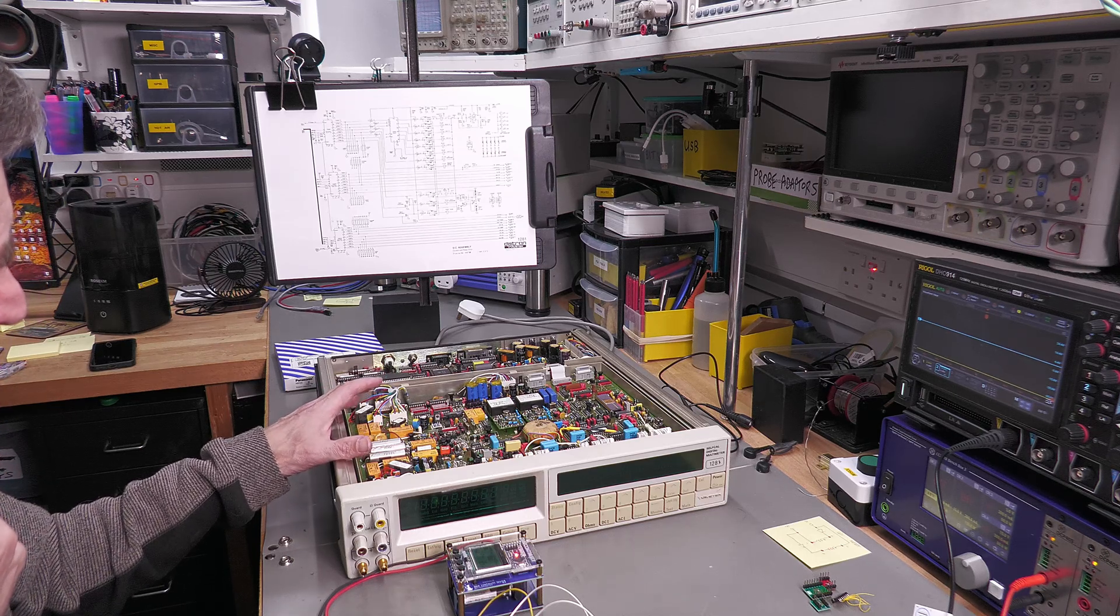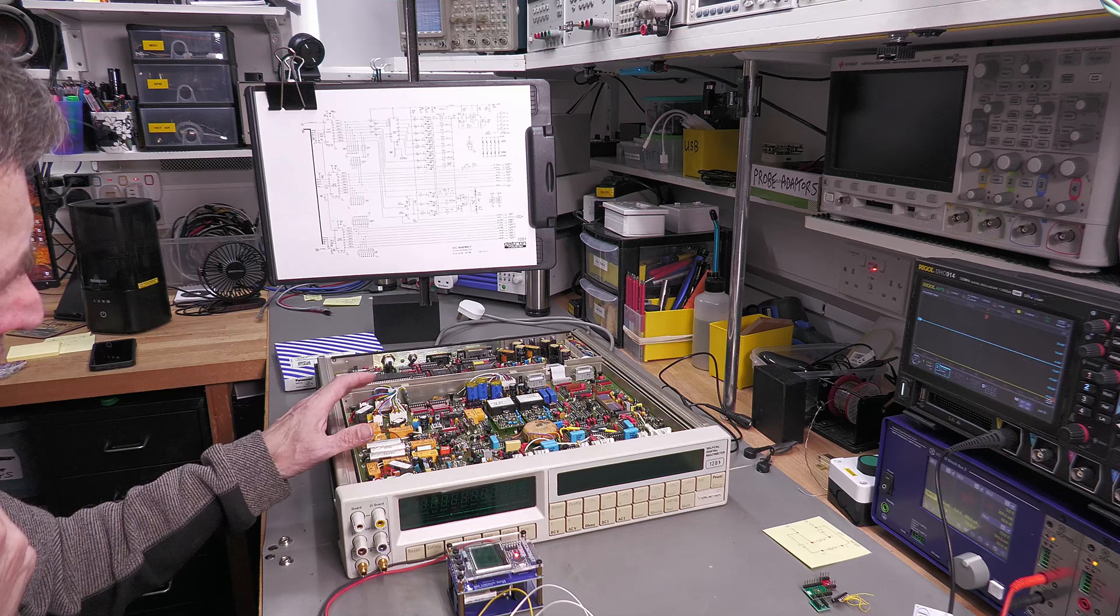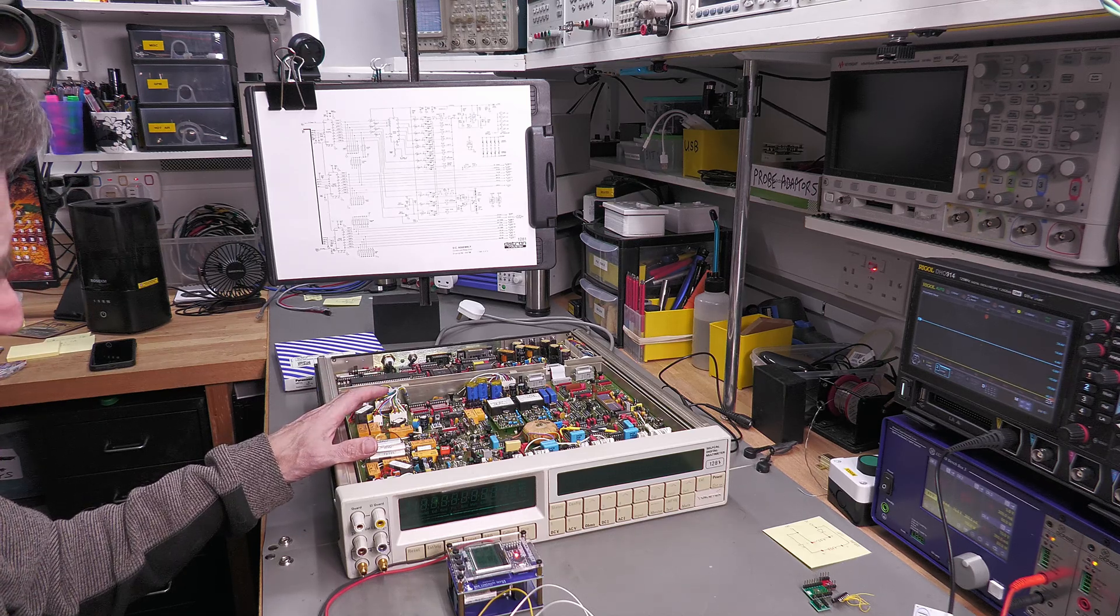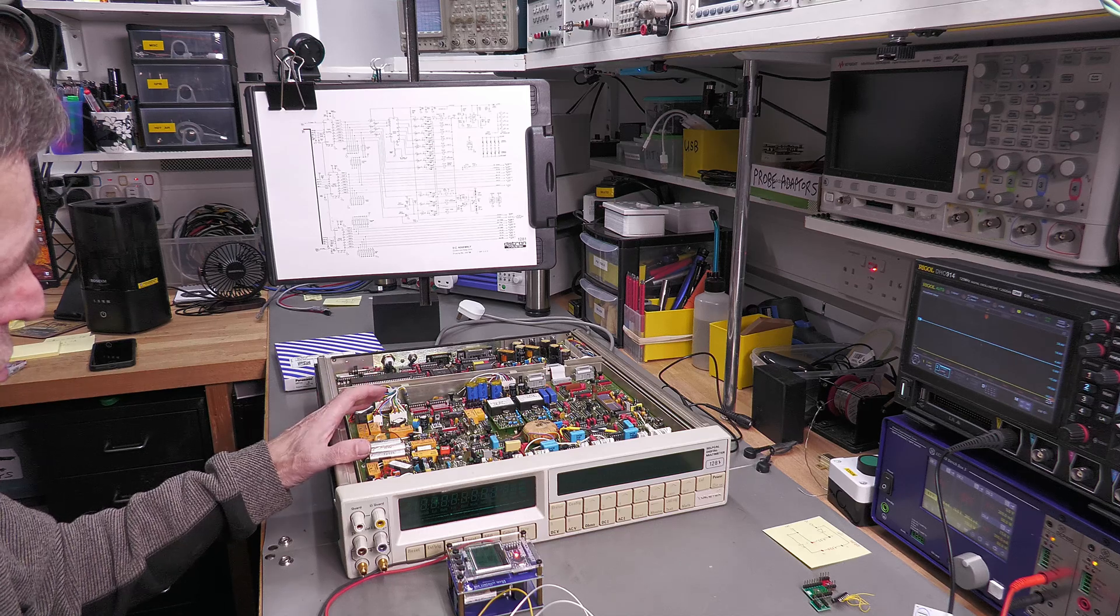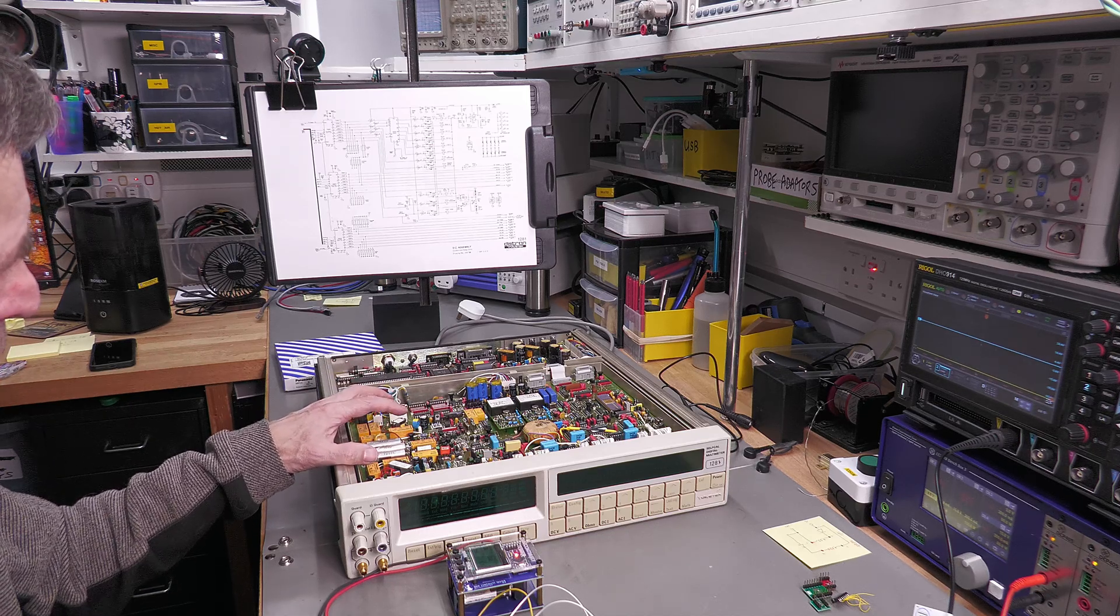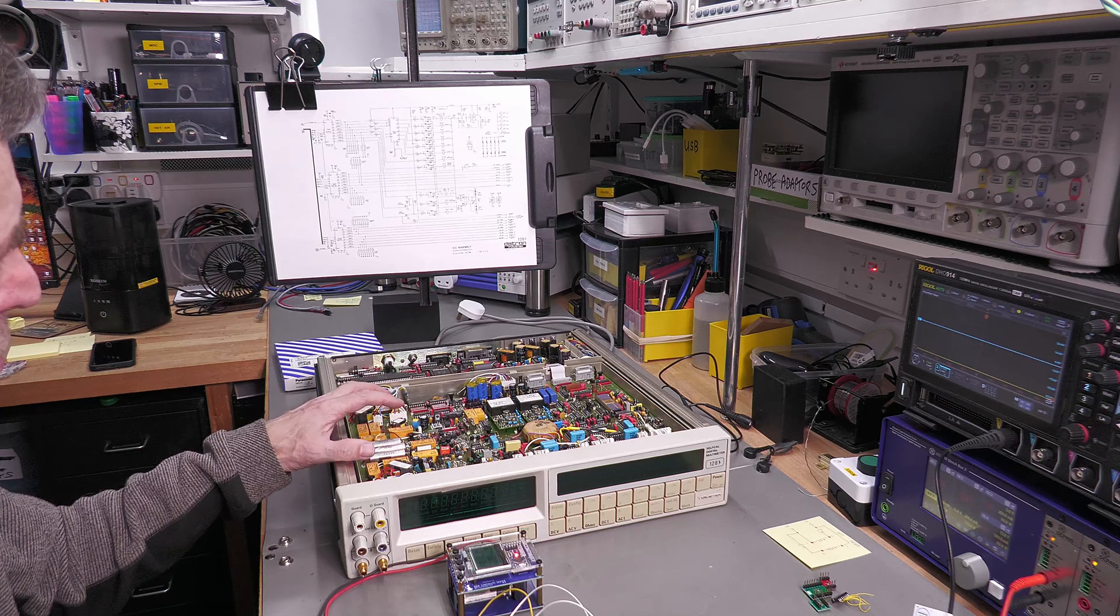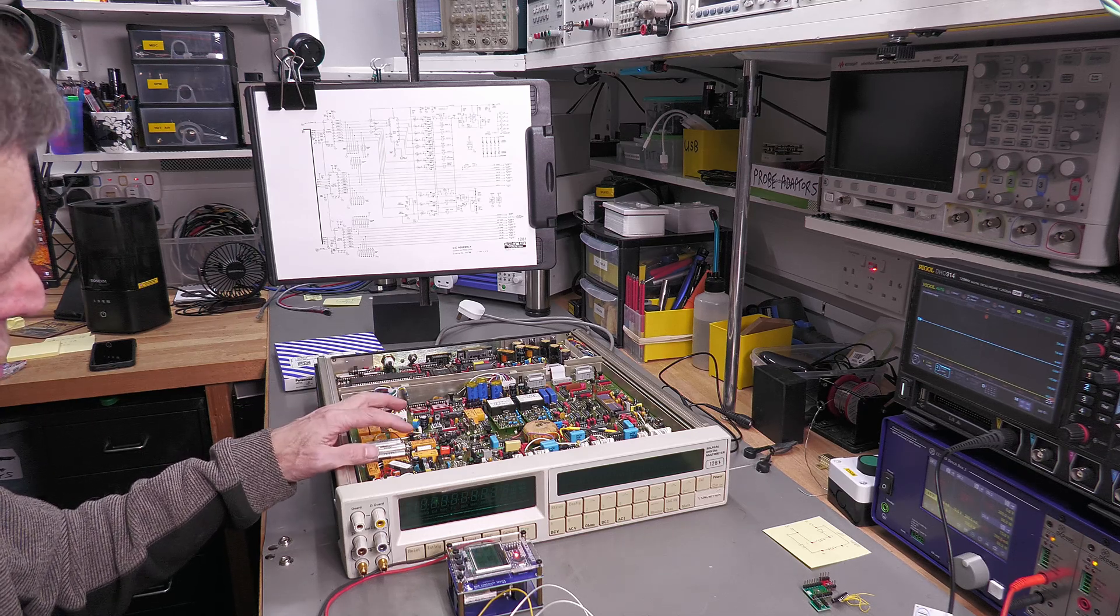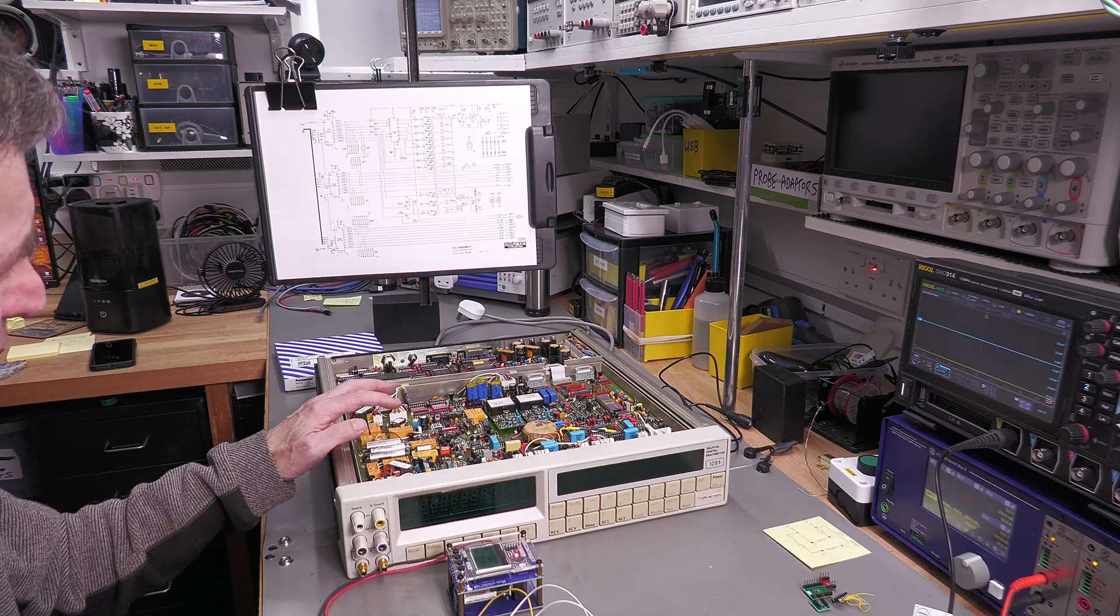Given the specification of the original relays, I came to the conclusion that the Panasonic relays that had been fitted are not suitable because they're dual coil set-reset relays, when the original relays fitted were actually single coil.